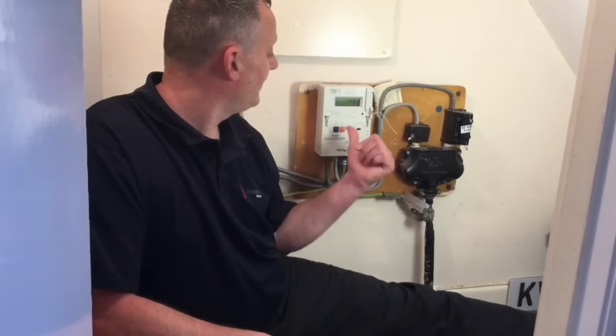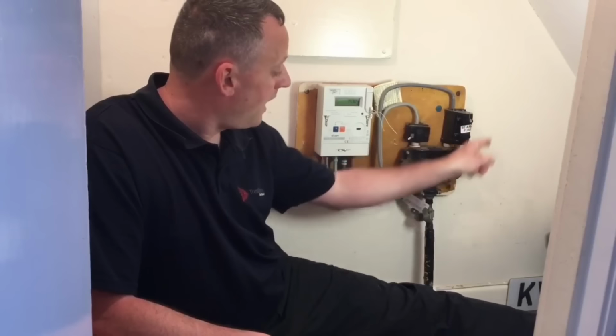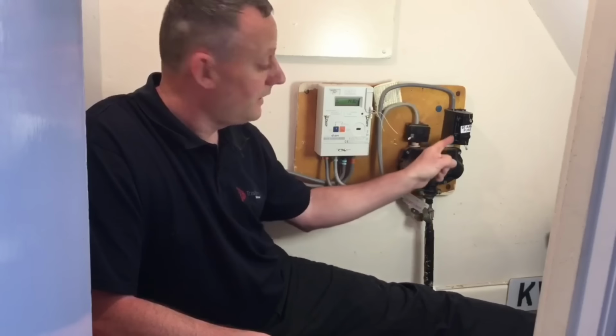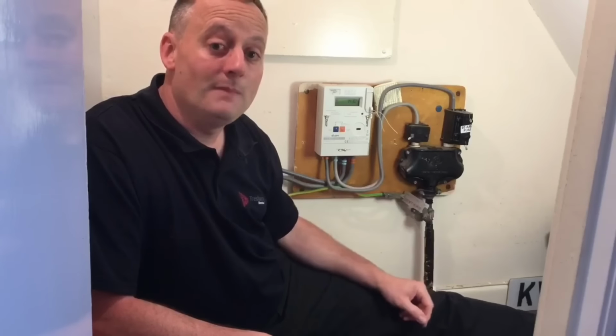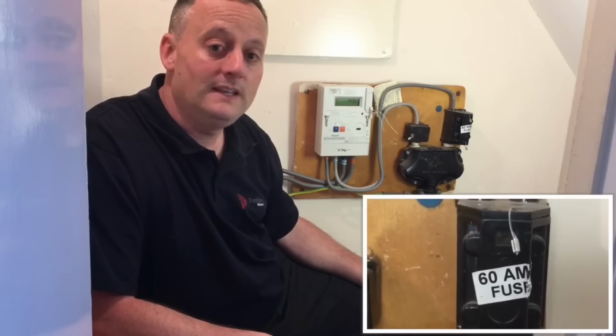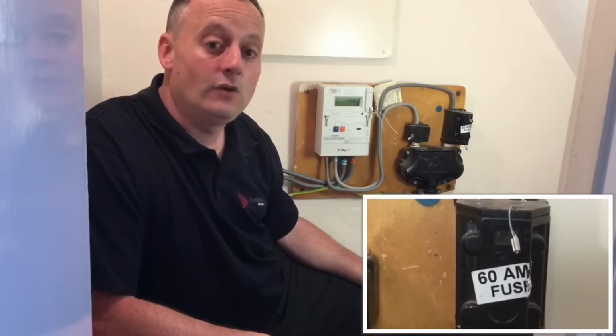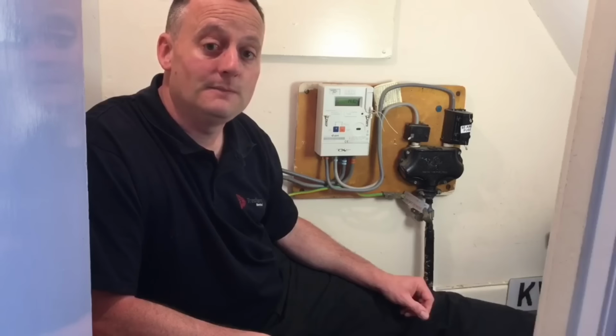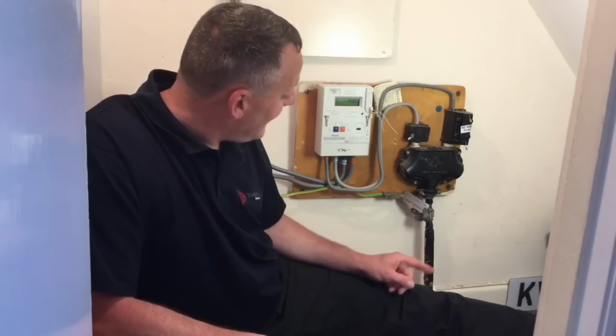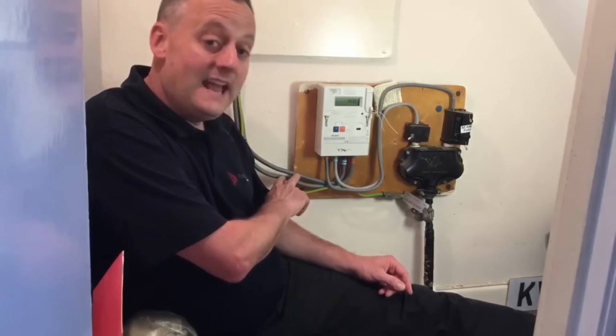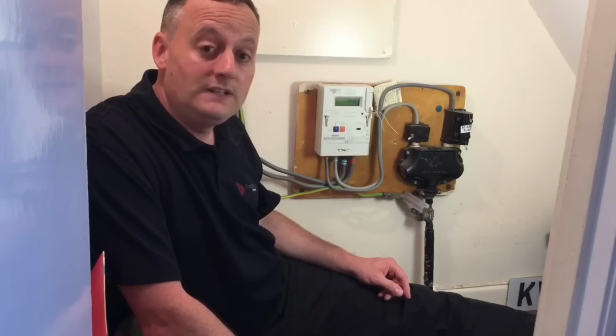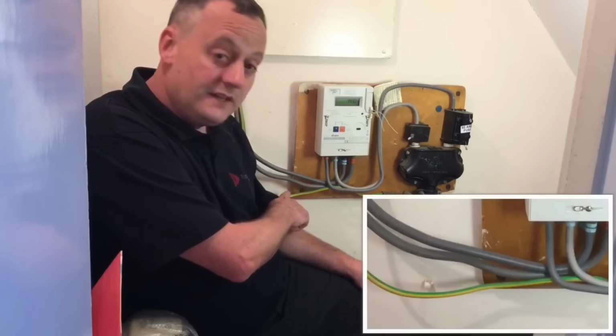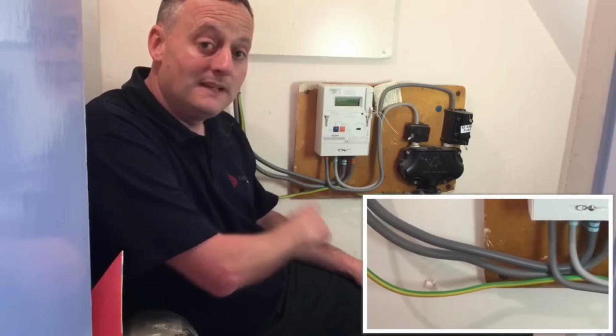So as before, we've got a kilowatt hour meter. We've got our cutout section here, including our cutout fuse, which this time is rated at 60 amps. Remember, it can either be rated at 60, 80 or 100 amps for a single phase domestic dwelling. We've got our tails to our consumer unit here, as before, sized at 25 millimeters squared, and our earthing conductor is sized at 16 millimeters squared.